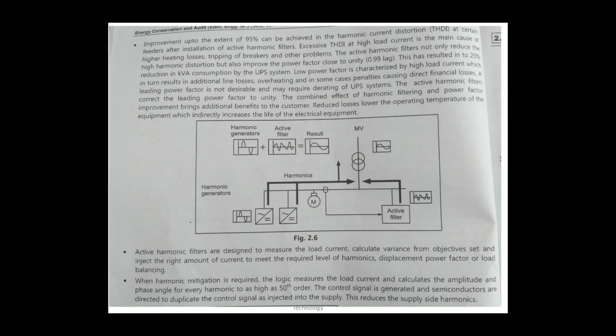breakers and other problems. The active harmonic filter not only reduces the high harmonic distortion but also improves the power factor close to unity, 0.99. This has resulted in a 20% reduction in kVA consumption by the UPS system. Low power factor is characterized by high load current, which in turn results in additional line losses, overheating, and in some cases penalties causing direct financial losses.